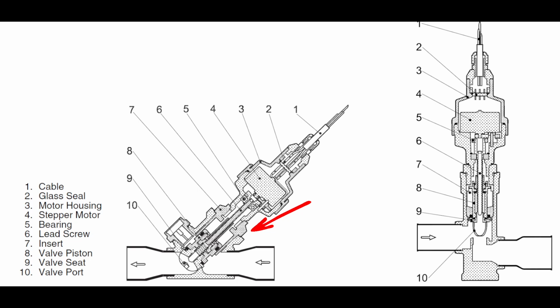And just keep in mind, even if you have a new valve, these things fail, and it's okay. It's just part of the process. I've had these valves last 1 to 2 months, and they just didn't hold up. There was actually a few. This is several years back at this point. The valves I was getting from York at the time. I did several valve repairs, and within a couple of months span, I ended up having to go back within 1 to 2 months of almost all of those jobs and warranty every one of those valves. And the only thing we could come up with was there was just a defect at the manufacturing level that didn't get caught.